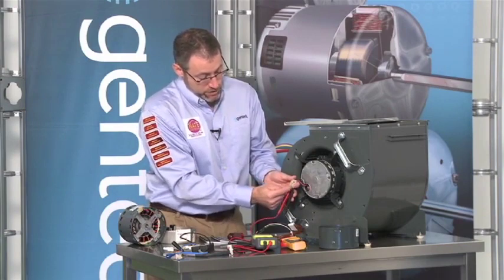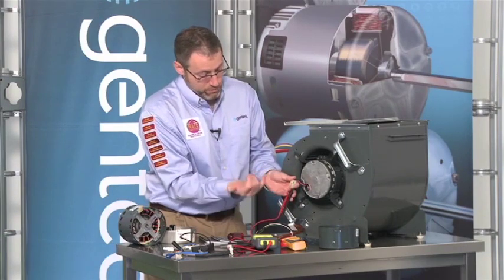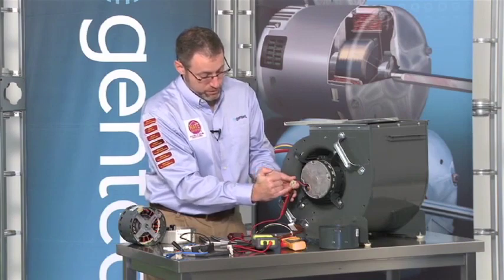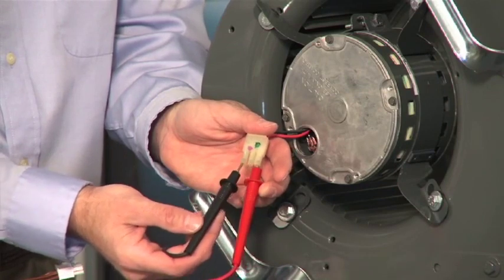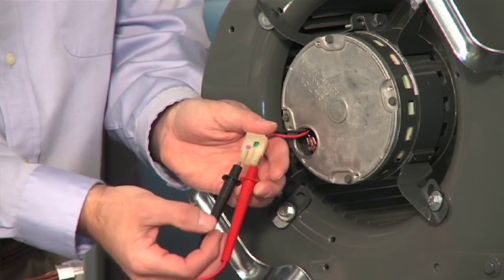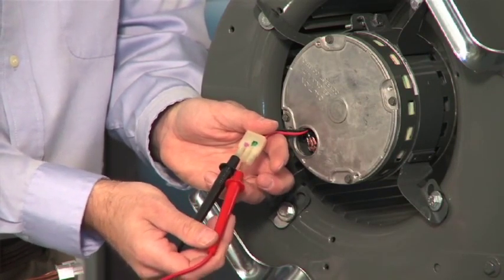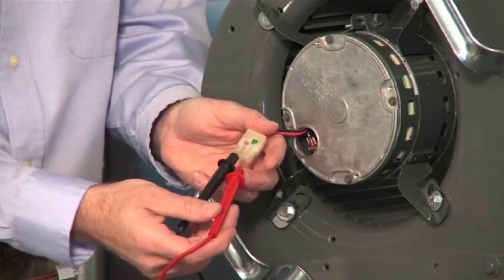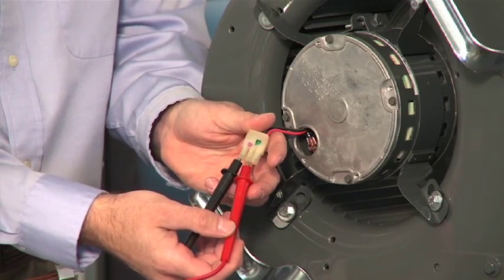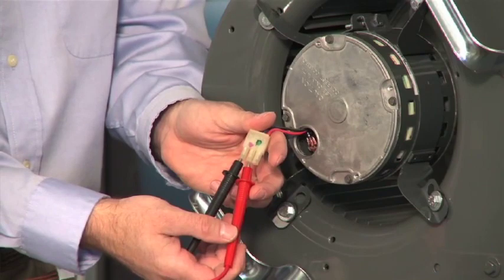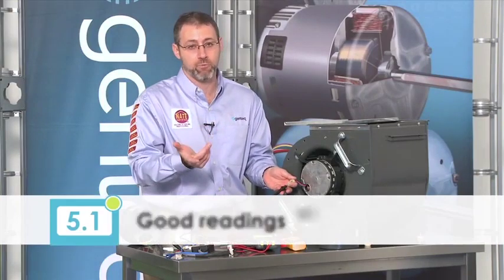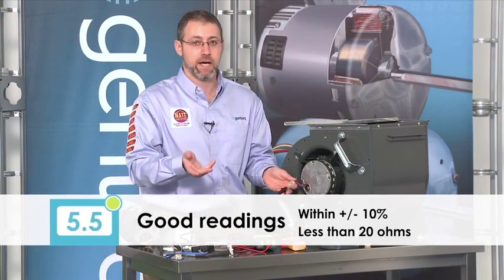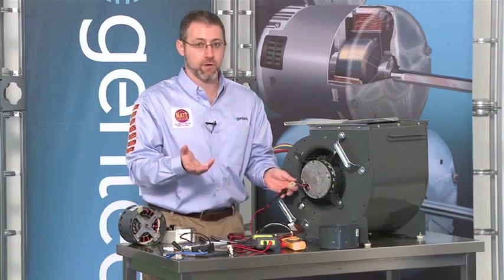So we would simply check 1 and 2, and then we're going to check 1 and 3, and then we're going to check 2 and 3. And if I read the same, plus or minus 10%, if I read like in the example you're looking at 5.1, 5.3, and 5.5, that's a perfectly good motor.